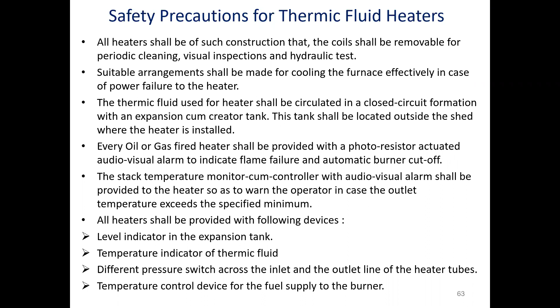Then the explosion vent for the heater shall be installed so that the release takes place at safe locations. So an explosion vent should be provided in that system. The maximum temperature of thermic fluid in the heating of the heater coil shall not exceed the figure specified by the manufacturer.